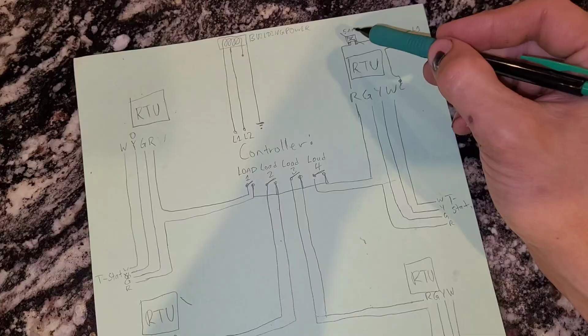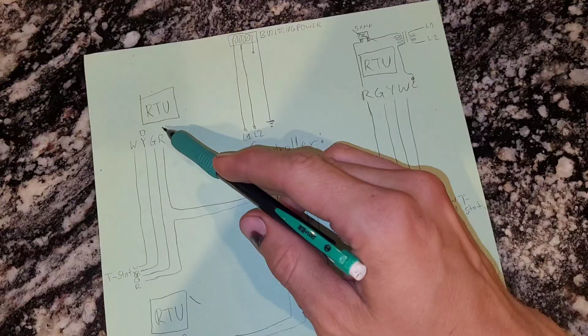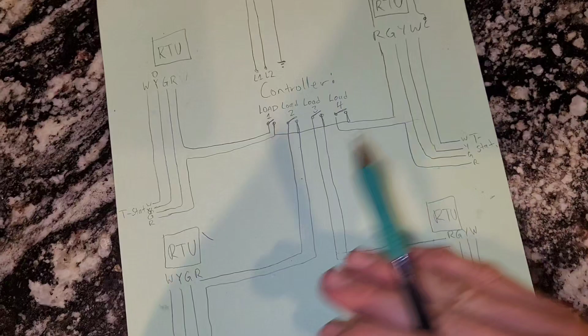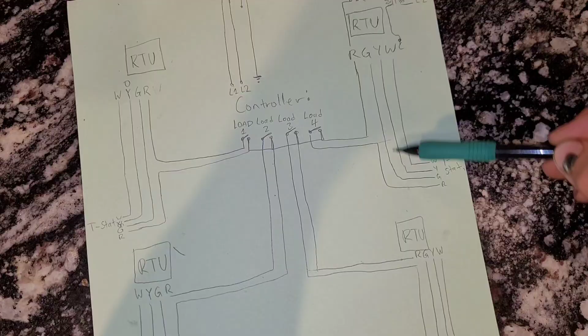We saw there was a burnt fuse here, and also then this rooftop unit, its 24 volts was feeding through the controller to the other rooftop units, which made it complicated to troubleshoot, coming from the controller on the R and going through the thermostat and then back up to the unit. So it just made troubleshooting and finding the actual problem kind of difficult.